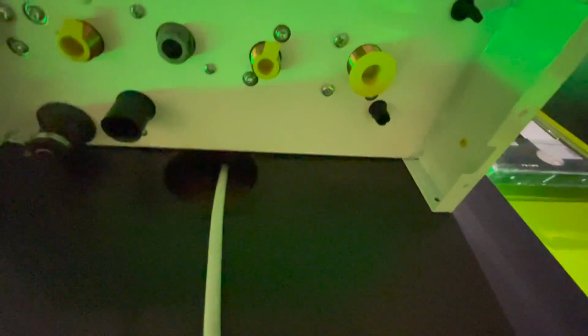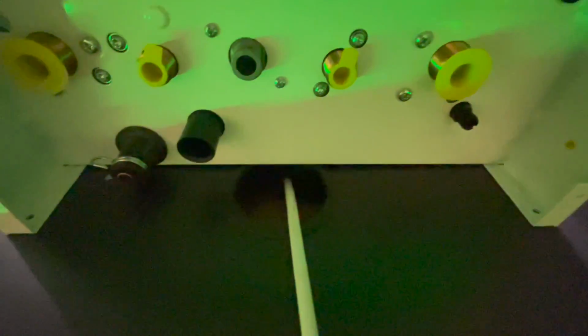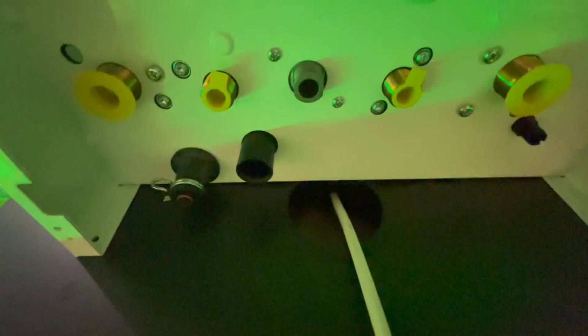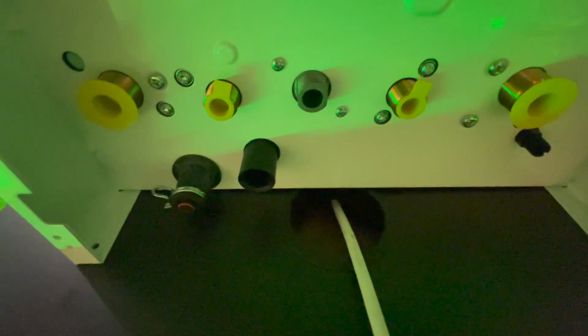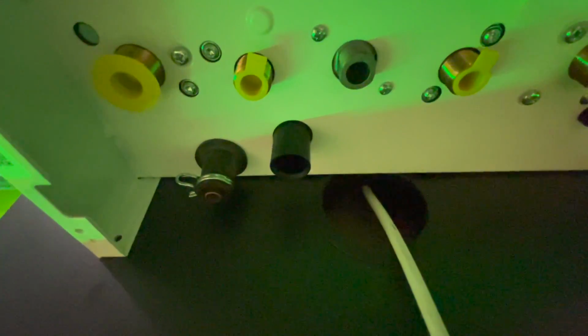So if we look underneath, you can see the flow, return, the gas, the hot and the cold are pretty much in the same location. But the condensate and the pressure relief discharge pipe have now moved, and the blow-off is now on the opposite side. So it's now on the left-hand side where it used to be on the right. And also there is now a quick release coupling for the blow-off. So no soldering needed here. You just literally put the swage pipe up and it clamps on.